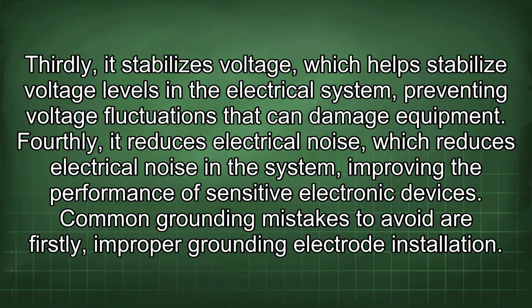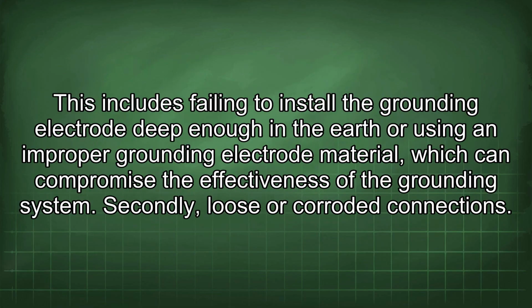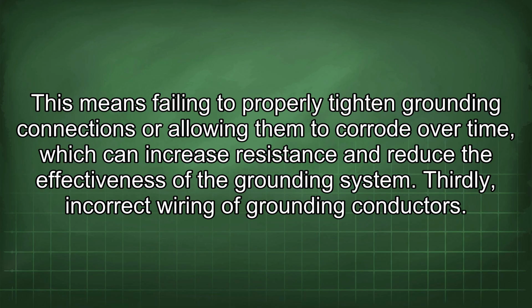Common grounding mistakes to avoid are, firstly, improper grounding electrode installation. This includes failing to install the grounding electrode deep enough in the earth or using an improper grounding electrode material, which can compromise the effectiveness of the grounding system. Secondly, loose or corroded connections. This means failing to properly tighten grounding connections or allowing them to corrode over time, which can increase resistance and reduce the effectiveness of the grounding system.